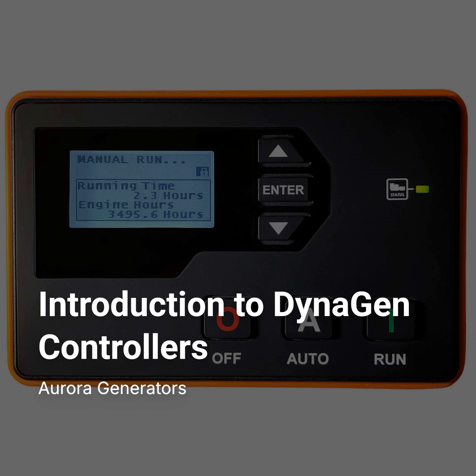Wow, really deep integration with J1939 and specific engine tech. And for people using Modbus, what kind of data can they get remotely? That separate Modbus reference manual lists all the registers. You can read data to monitor or write data for remote control, a wide range of things. You can remotely send start-stop commands, read real-time engine speed, temp, pressure, fuel level, generator frequency, voltage, current, get the current operating state, active warnings, events, and the maintenance counter value, and lots more.